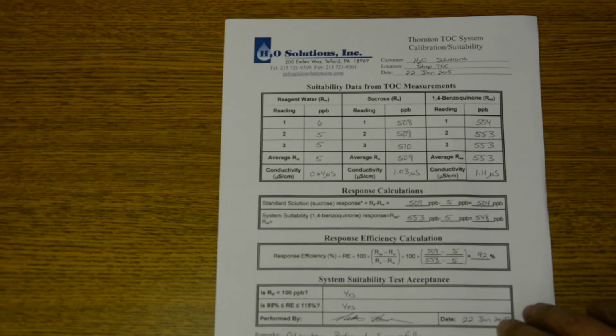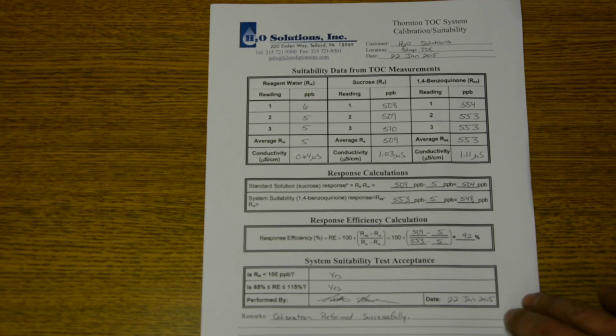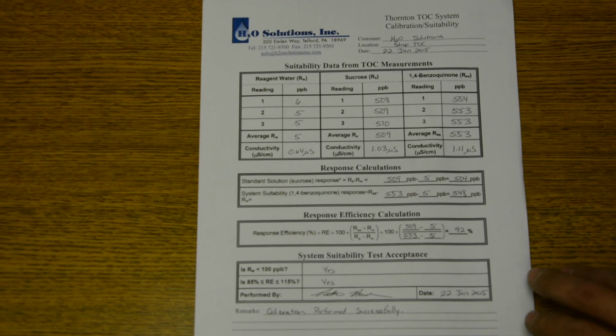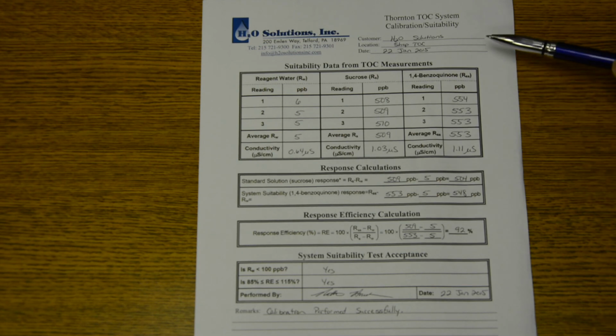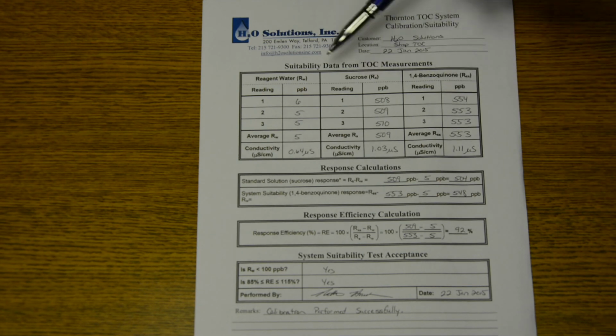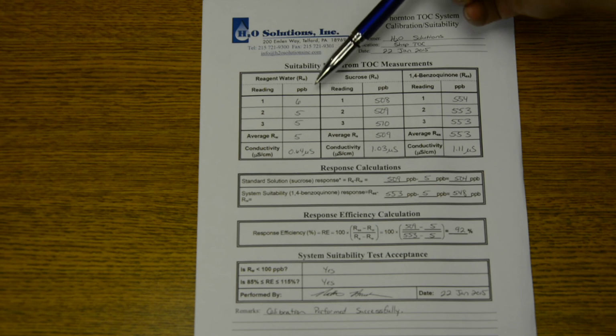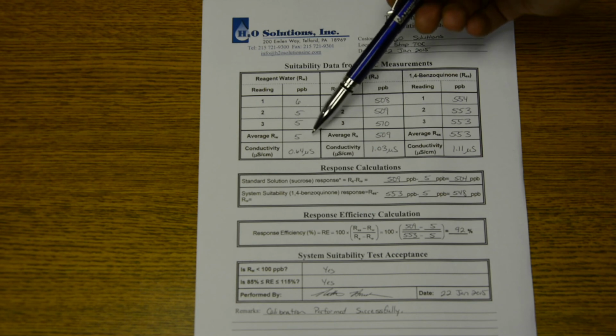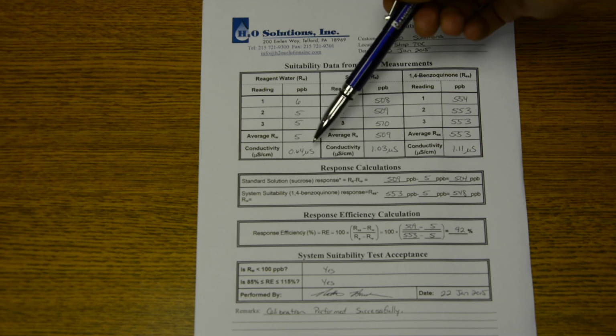On the back side of this page is where you will find all of your information for the suitability test. You have the same information located on the top of the page. The next boxes here are the different readings that we took. First column is for the reagent water that we used, your first reading, second reading, third reading, then your average reading where you take all 3 of those, add them, then divide them by 3. Then your conductivity reading, and that's not an average, we just take that one time during the test.